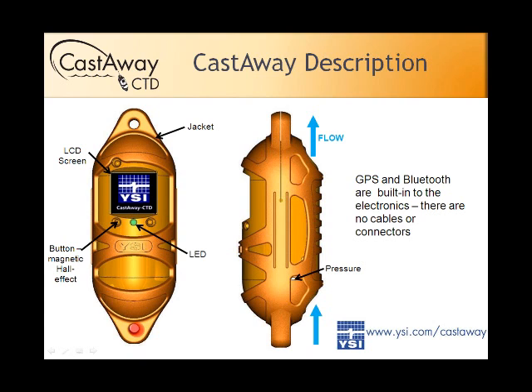This is a flow-through sensor — the cell is actually inside, with nothing protruding for things to get caught on. The buttons are magnetic Hall-effect — there's no physical actuation. The button isn't actually pushing in; you just get near it with the magnetic stylus. It is recessed so you don't accidentally trigger one of those buttons, but you just need to get the magnetic stylus nearby.